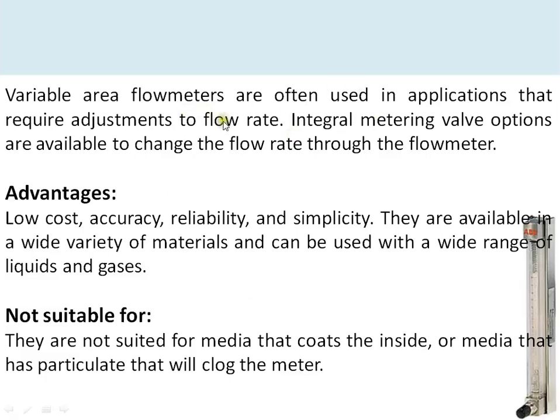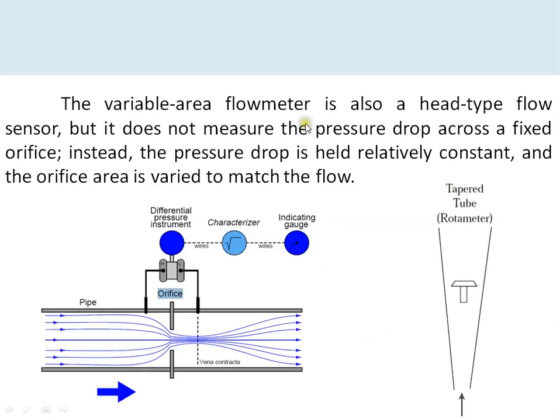Variable area flow meters are often used in applications that require adjustment to flow rate, because most rotameters come with a needle valve, so along with flow indication they also provide a means of controlling the flow rate. The advantages of rotameters are low cost, accuracy, reliability, and simple construction. They are not suitable for media that coat the inside of the tube or media containing particulates, as these will obstruct the movement of the float and give incorrect readings.